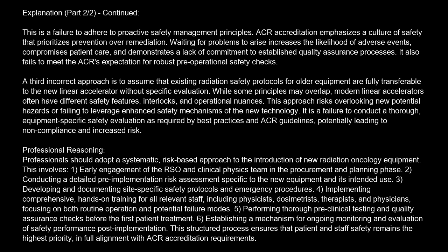3. Developing and documenting site-specific safety protocols and emergency procedures. 4. Implementing comprehensive hands-on training for all relevant staff, including physicists, dosimetrists, therapists, and physicians, focusing on both routine operation and potential failure modes. 5. Performing thorough preclinical testing and quality assurance checks before the first patient treatment. 6. Establishing a mechanism for ongoing monitoring and evaluation of safety performance post-implementation. This structured process ensures that patient and staff safety remains the highest priority, in full alignment with ACR accreditation requirements.